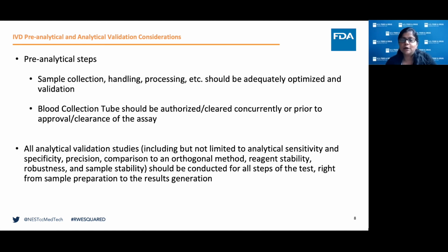And again, this is a whole new different topic by itself. So all analytical validation studies should be conducted for all steps of the test, right from sample preparation to results generation, and intended use clinical specimens should be used for all these different validation studies, unless otherwise specified that there is a limitation of the intended use clinical specimen, wherein you may use contrived samples or cell lines, but the functional behavior between the clinical and the contrived samples should be demonstrated.